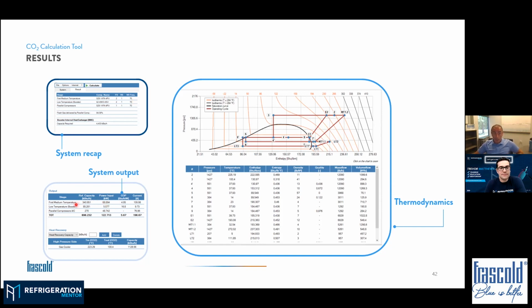It also gives us the real capacity it's delivering. Of course we're not matching the exact number we're looking for, but pretty close. Then you can refine your selection by changing a compressor. For example, here we're selecting a compressor delivering the capacity at 70 hertz. Probably it would be wiser to select a bigger compressor delivering the capacity at 65 hertz instead. So this is something you can refine, and after you run the first selection, it gives you a rough idea of what's giving you the capacity you're looking for.